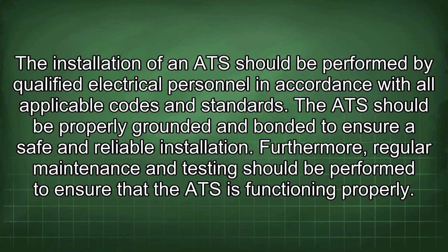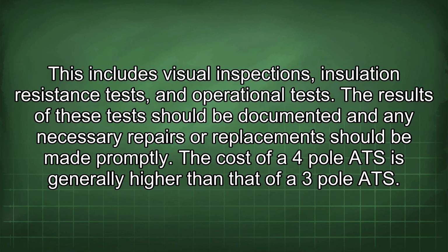Furthermore, regular maintenance and testing should be performed to ensure that the ATS is functioning properly. This includes visual inspections, insulation resistance tests, and operational tests. The results of these tests should be documented, and any necessary repairs or replacements should be made promptly.